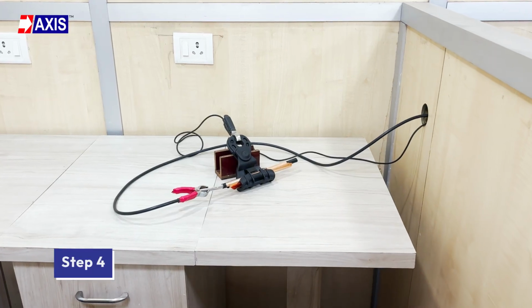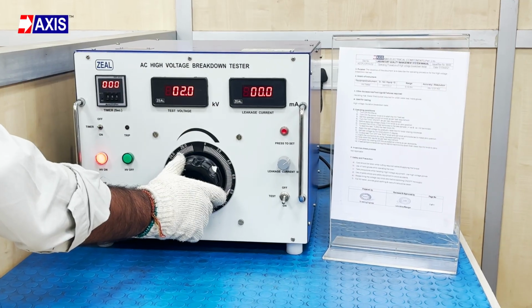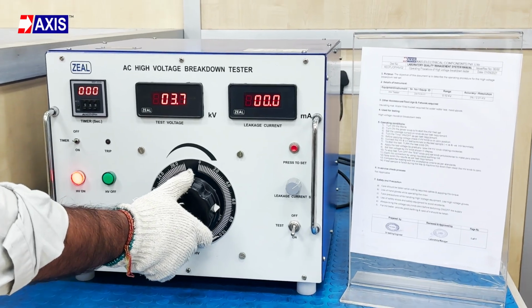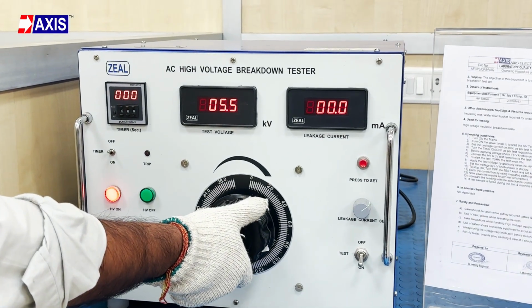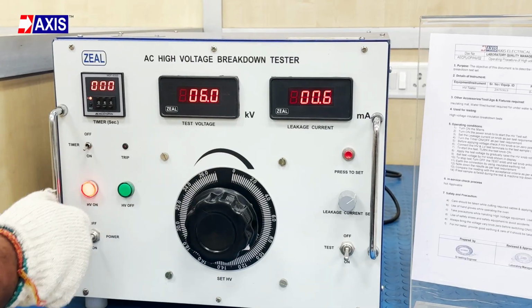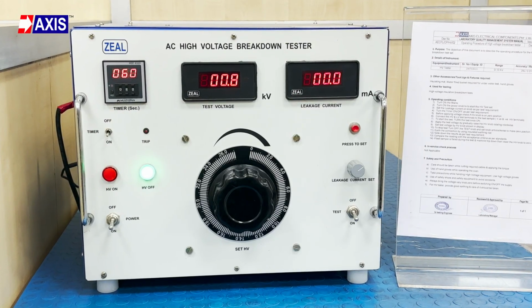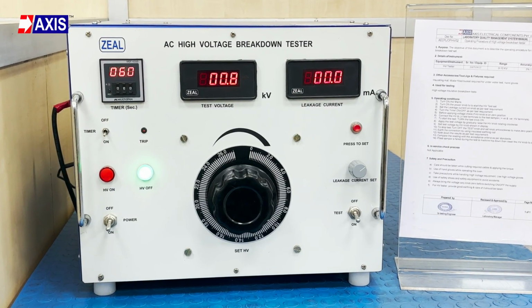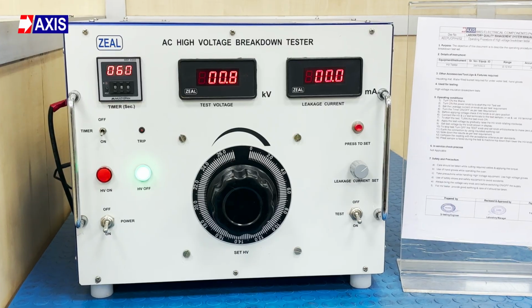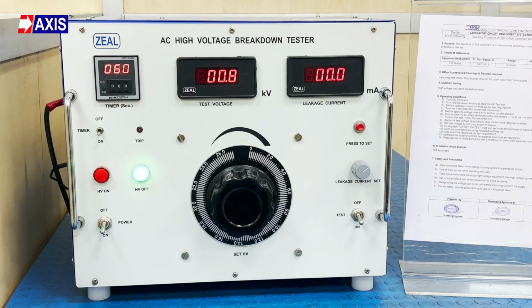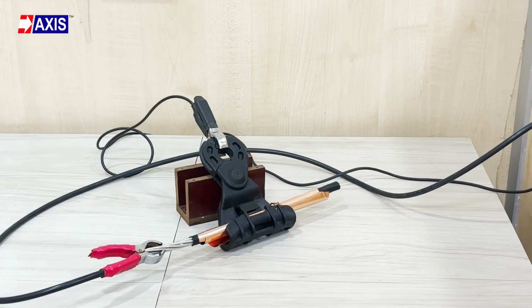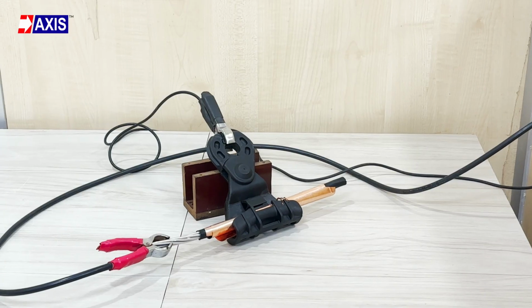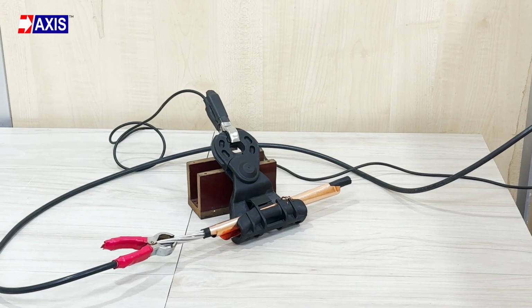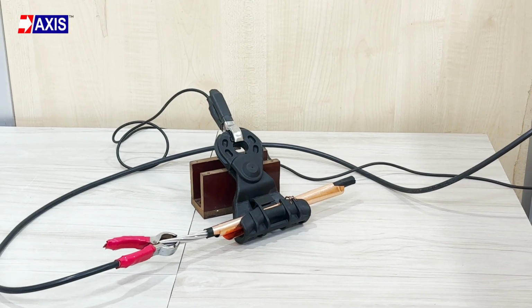Step 4. Gradually increase the alternating current test voltage to 6 kV at a rate of approximately 1 kV per second. Maintain the voltage for 60 seconds. The maximum leakage current shall be equal to 10 mA plus or minus 0.5 mA. Observe the sample during testing. The clamp passes if there is no flashover, no breakdown, and no surface discharge.